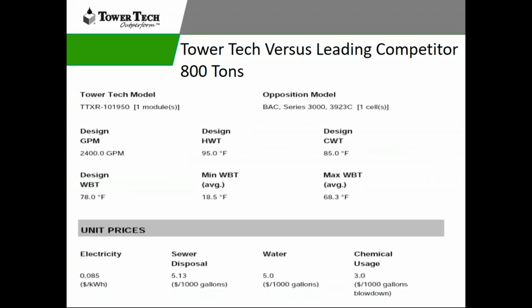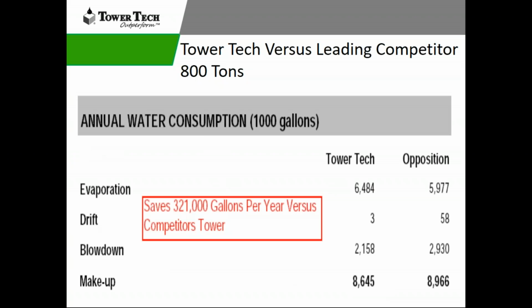Now I'm going to analyze the Tower Tech solution. Let's say we have a tower that has to be replaced. It is a water-cooled system, and it's staying water-cooled. We want water-cooled. In this case, we have an 800-ton system comparing it against one of our competitors. So we're using an electrical rate of 8 cents per kilowatt hour, a sewer cost of $5.13, water cost, we have a total combined cost of $10.13 per 1,000 gallons, and then we have a chemical usage cost. When we do this analysis at 800 tons, we are going to save that end user about 321,000 gallons per year on the water side of it, in this case.